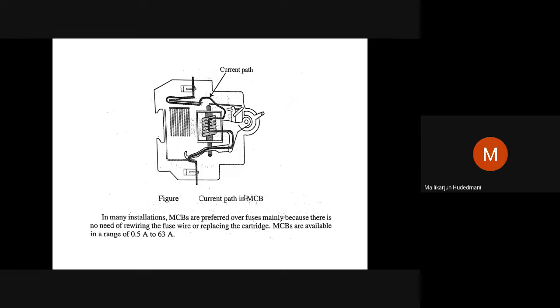Then what is that? It is the same miniature circuit breaker I am speaking about. The shape and size is different, but the concept is a bimetal strip whose deformation breaks the electric circuit contacts, which makes for the safety of the device. If that mixer grinder thermal strip was not provided, can you see your mixie remaining for your next usage? Definitely it may not be there. Therefore, to protect electrical devices on overdrawal of current, some safety precautions need to be utilized.